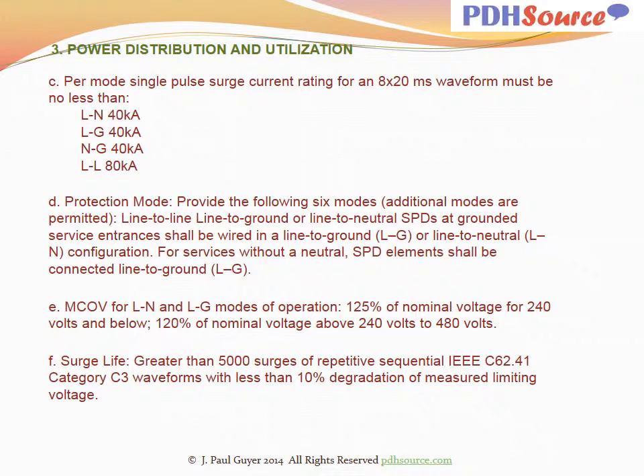Protection mode, provide the following 6 modes. Additional modes are permitted. Line to line, line to ground, or line to neutral SPDs at grounded service entrances shall be wired in a line to ground or line to neutral configuration. For services without a neutral, SPD elements shall be connected line to ground.